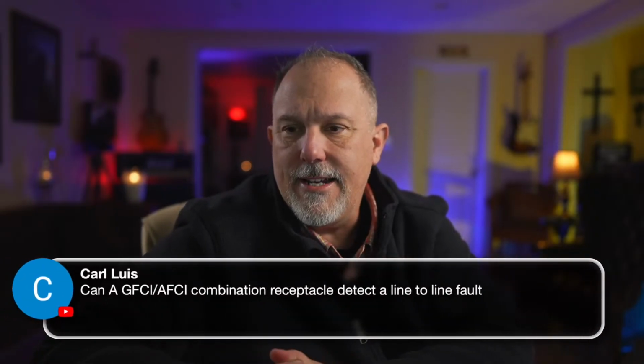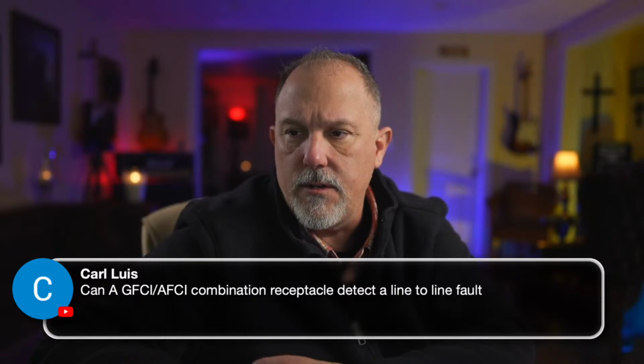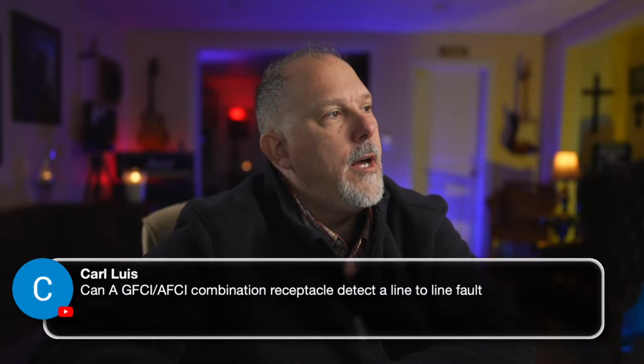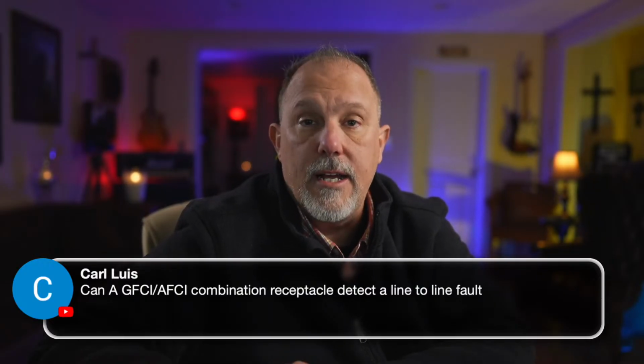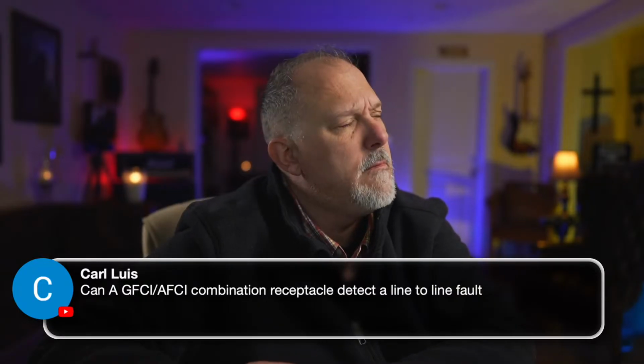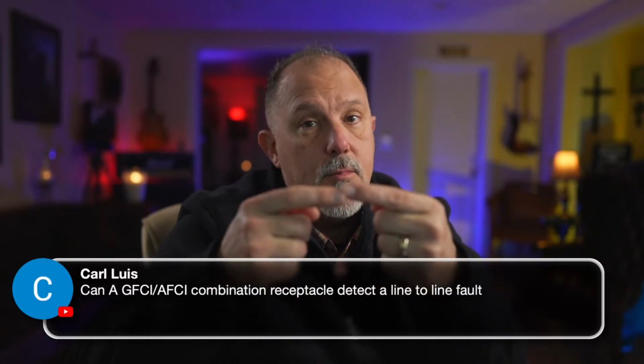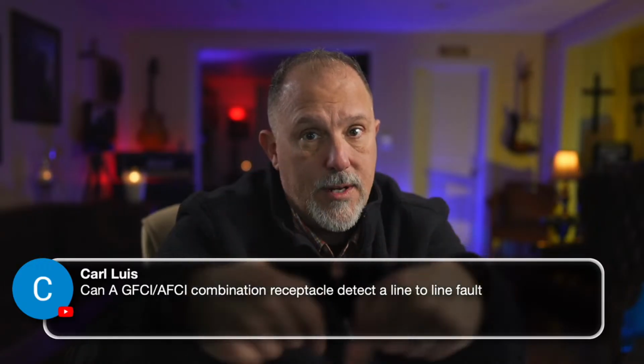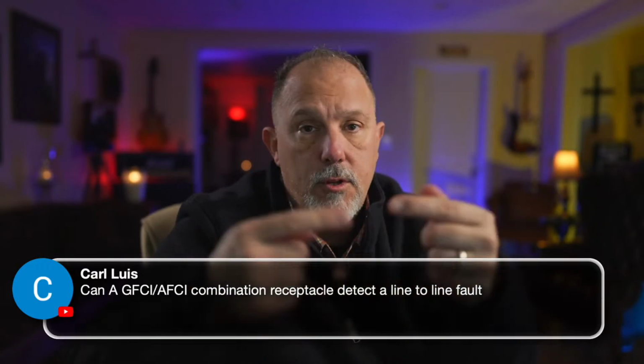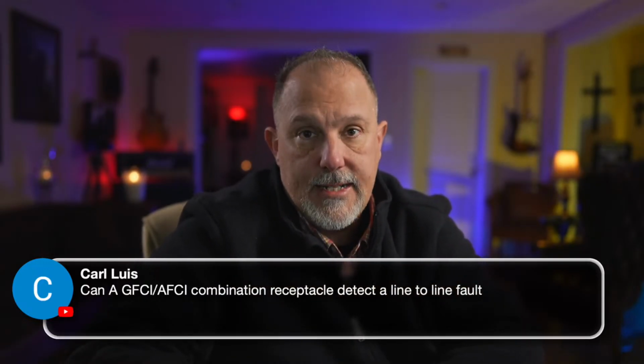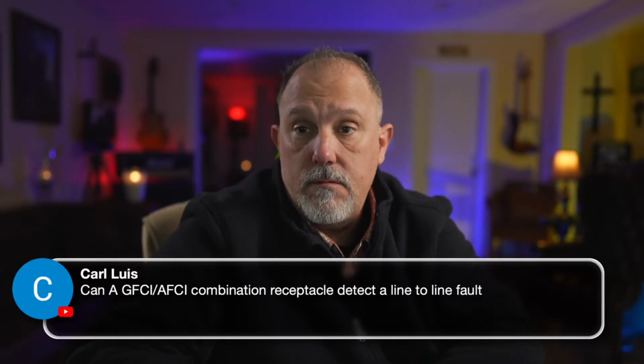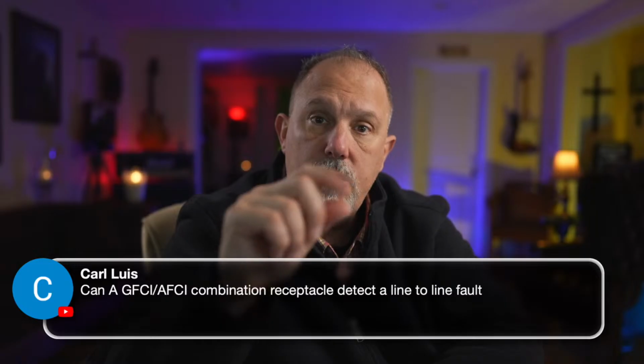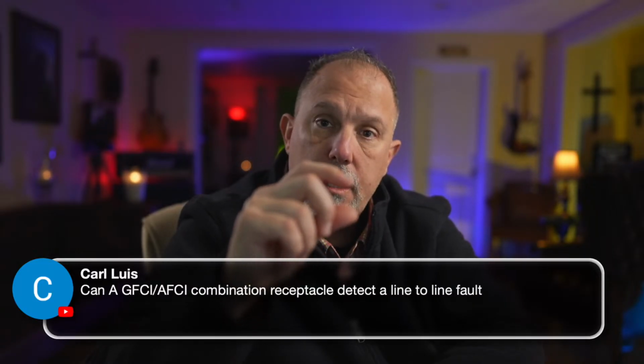Carl Luis asks, can a GFCI AFCI combination receptacle detect a line-to-line fault? GFCI definitely not. If it's a line-to-line fault, it's not going to see it. Now remember, with line to line, the moment you bring the ground in, it's now going outside the path. But line to line is not a ground fault. An arc fault will only detect it if it's an arcing fault.